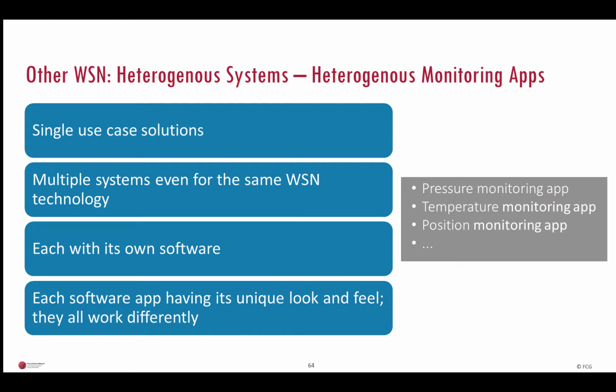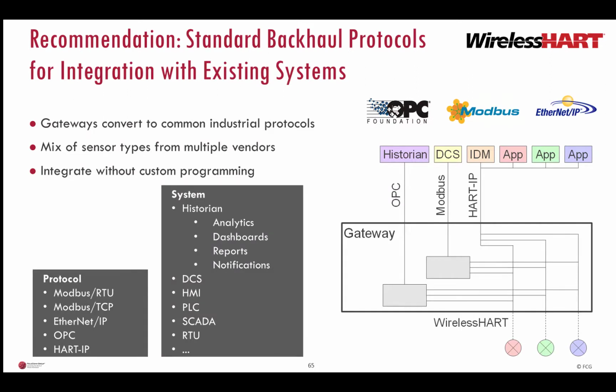Other wireless sensor network solutions offered by vendors often tend to be a single use case. So even with the same technology, you end up with multiple heterogeneous systems, with one software to monitor pressure from one vendor, another for the temperature sensors from another vendor, a third for level, and so on. So this mix of software makes the data harder to use, so may fall into disuse. So be careful. WirelessHART solves this by using the standard HART application protocol, which has a common message format and common data types for all WirelessHART sensors, regardless of manufacturer and sensor type.